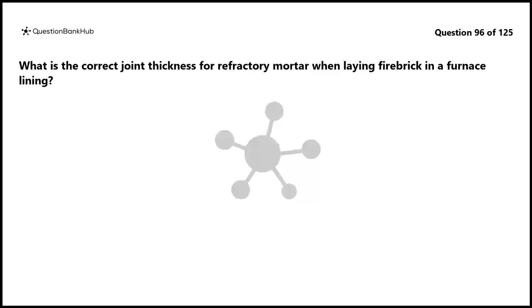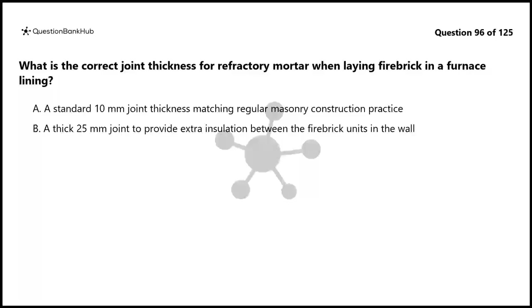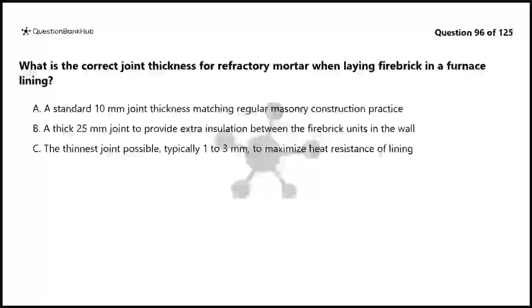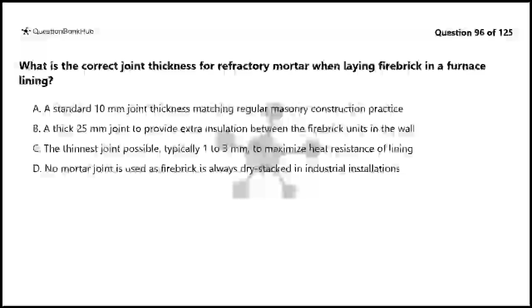Question 96. What is the correct joint thickness for refractory mortar when laying firebrick in a furnace lining? A. A standard 10 mm joint thickness matching regular masonry construction practice. B. A thick 25 mm joint to provide extra insulation between the firebrick units in the wall. C. The thinnest joint possible, typically 1 to 3 mm, to maximize heat resistance of lining. D. No mortar joint is used as firebrick is always dry stacked in industrial installations.